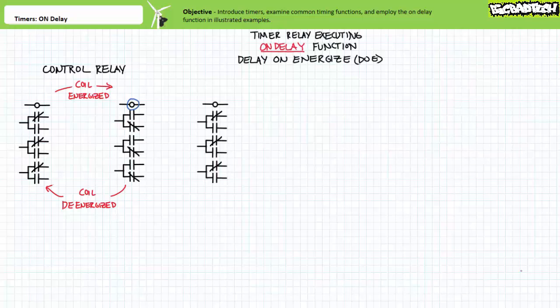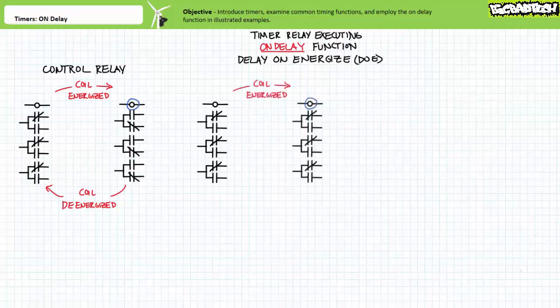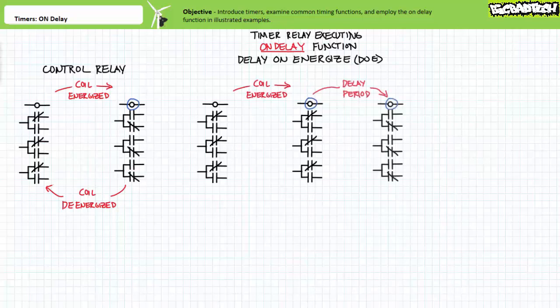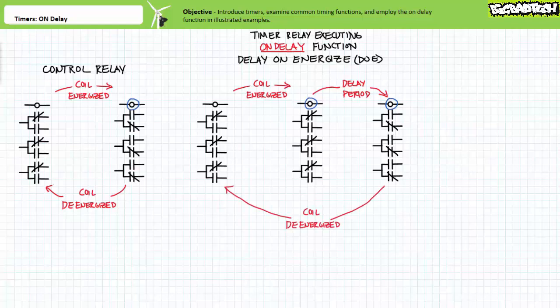Now consider a timer relay, also with a coil and a set of associated single pole double throw transfer contacts, executing the on-delay function, sometimes called delay on-energize or DOE. When the timer relay coil is energized by pilot voltage, the associated contacts do not respond instantaneously, but only after a predetermined delay period has elapsed. When the coil is de-energized, the contacts quasi-instantaneously revert to their natural deactivated state.